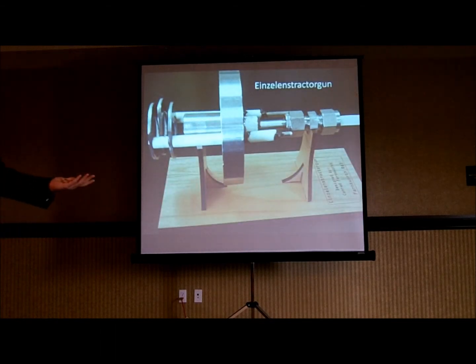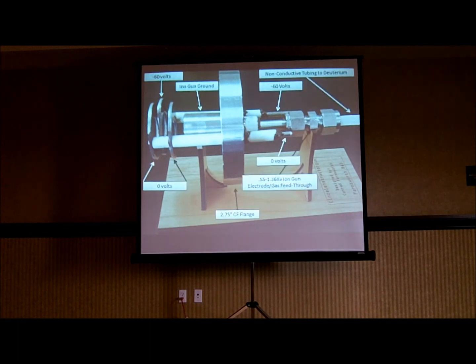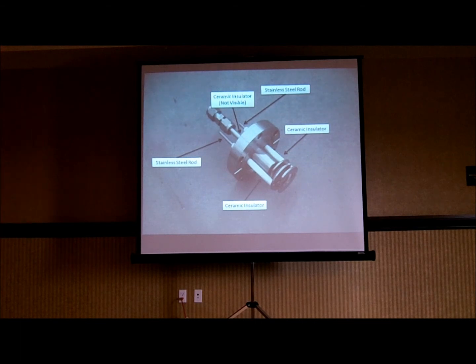Moving on further, here's the Einzel lens extractor gun, as I have previously mentioned. It's composed of a 2.75-inch conflat vacuum flange, which I have machined and fitted with various ceramic insulators and stainless steel electrodes. As you can see at the front of the gun, we have 2 plates at 0 volts and a center plate at negative 60 volts, and I'll get into this later. Moving back, we have the ion gun segment. The flange is where it ends the vacuum, and here's regular atmospheric pressure. Then we have the ion gun connection for the high voltage, and then we have a non-conductive tube to the deuterium gas supply. Moving on, here's another view.